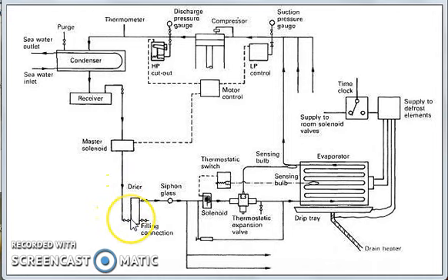The dryer's main work is to eliminate any moisture present in the refrigerant, because this moisture can lead to frosting in the expansion valve, and hence the temperature of the room will not come. If the thermostatic expansion valve gets moisture and gets iced, then the refrigerant will not flow from the expansion valve to the evaporator and we will not get the desired temperature of the room.